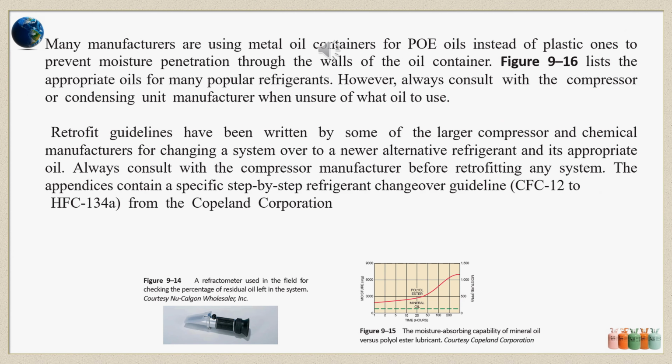Many manufacturers are using metal oil containers for POE oils instead of plastic ones to prevent moisture penetration through the walls of the oil container. Figure 9-16 lists the appropriate oils for many popular refrigerants. However, always consult with the compressor or condensing unit manufacturer when unsure of what oil to use.